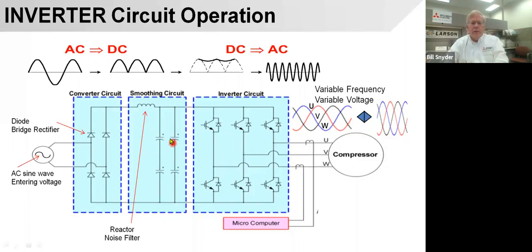Then we go to these devices here. Now what these are, capacitors. They're smoothing capacitors. And they actually smooth the circuit out a lot. The way a capacitor works is as you apply power to it, it absorbs the energy, and when you start to remove power away, it discharges. So as the power goes up a little bit, we're absorbing, and then we're discharging. So it's taking this signal here and making it a very, very flat signal. It's a very good DC signal. So then we're coming out of here with DC voltage. And typically that voltage is around 300 volts DC.